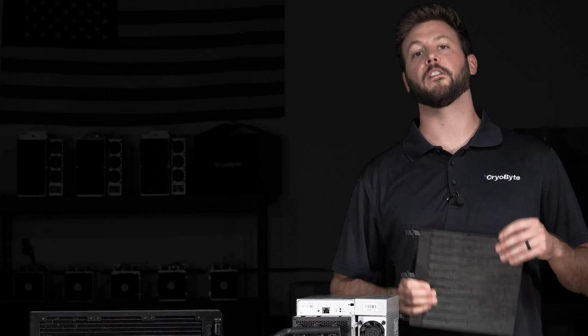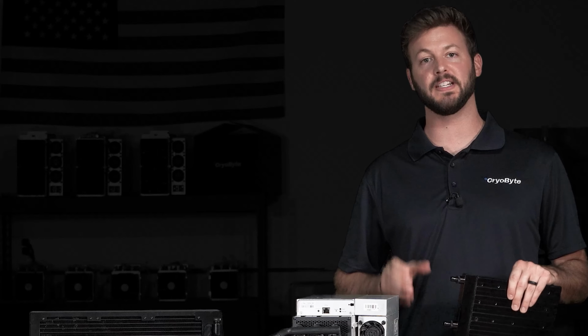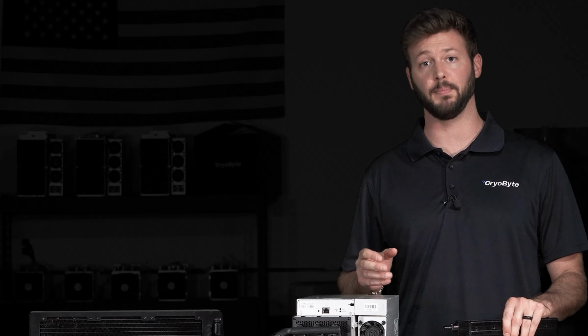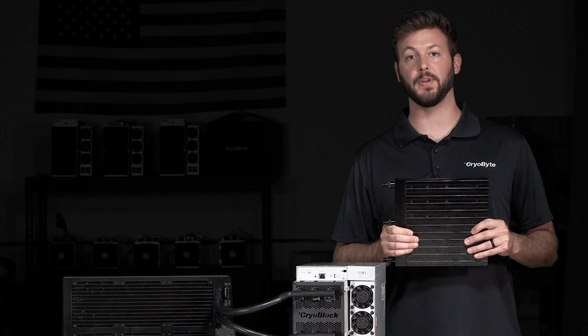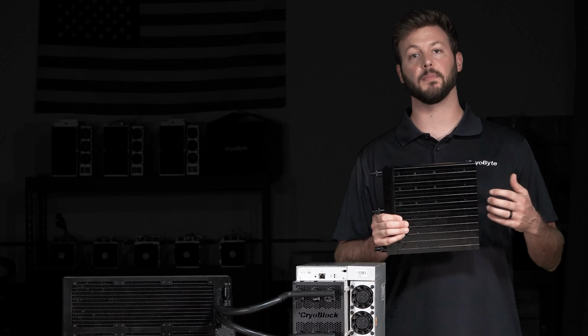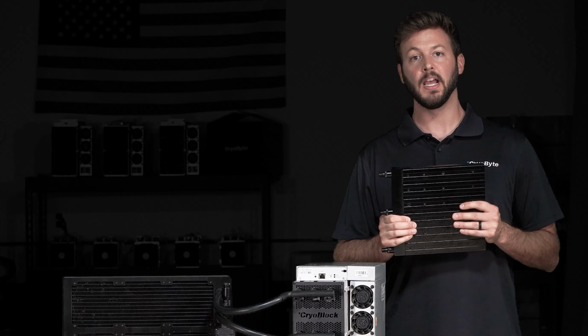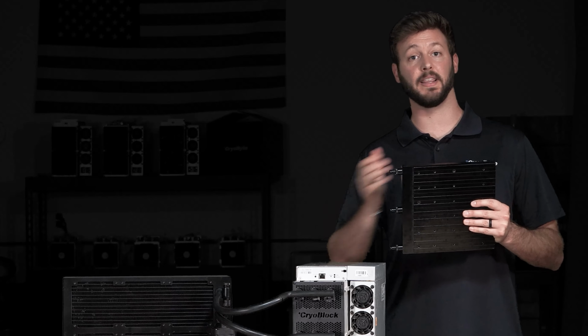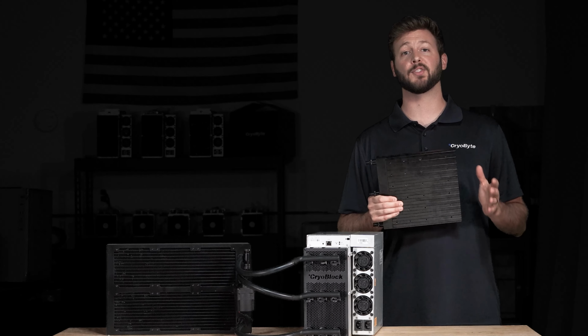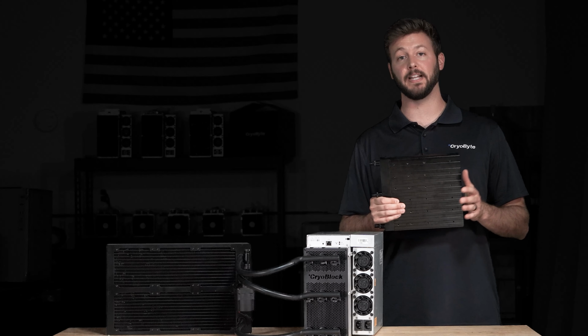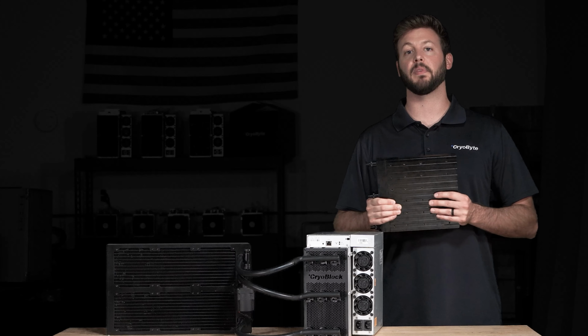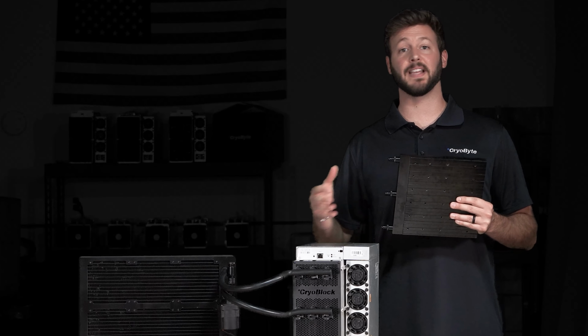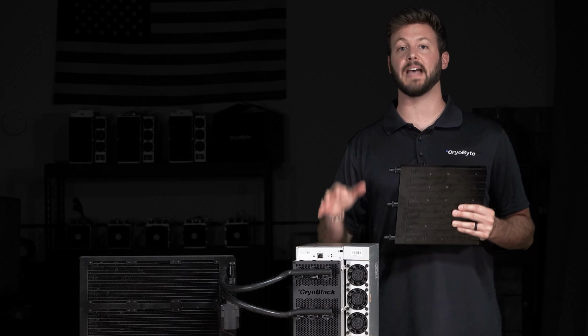Quick nerd out: your cooling efficiency is largely dictated by the difference in temperature between your hot load and your coolant. The larger the difference, the better the cooling effect. So in a hybrid cooled unit, we move cool water from back to front of the hashboard while pulling cool air from front to back of the miner. This creates a cross cooling effect that targets and eliminates hot spots while providing some of the most even temperatures. That's why sensors throughout this unit read almost the exact same temperature.